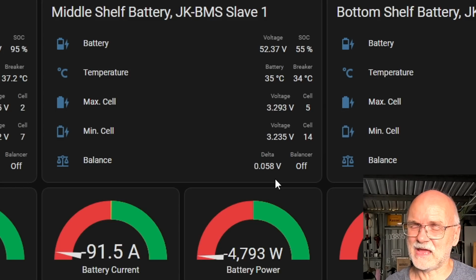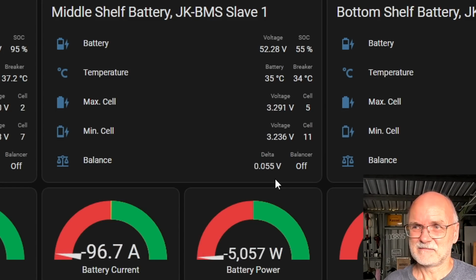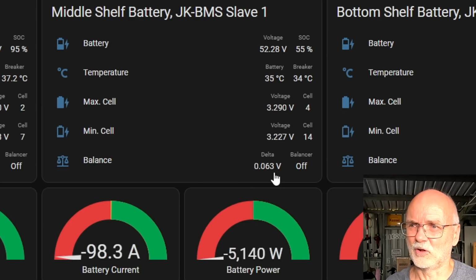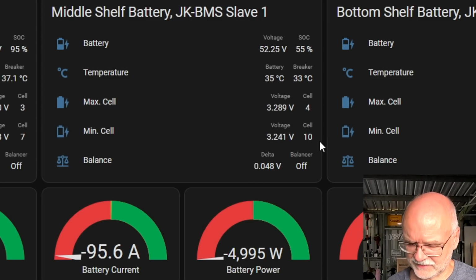So obviously there is a problem with these terminals, oxidation, some sort of issue going on underneath. 55 millivolt, 63 at 5.1 kilowatt. Well, at least it's jumping back and forward now. Cell number 14, before it was cell number 11, 10.